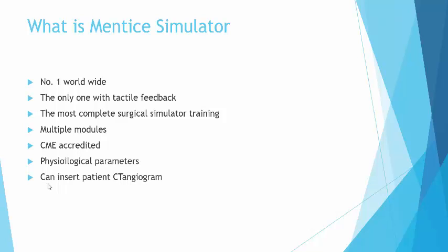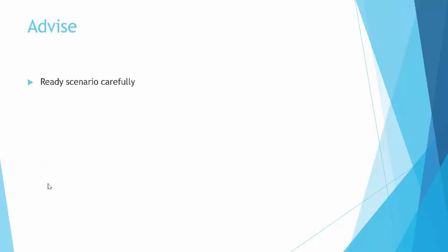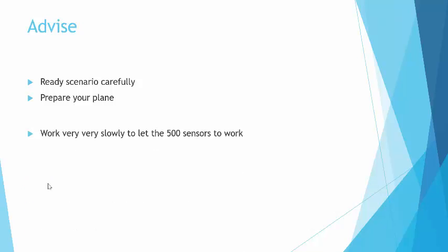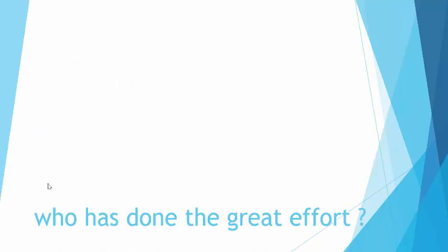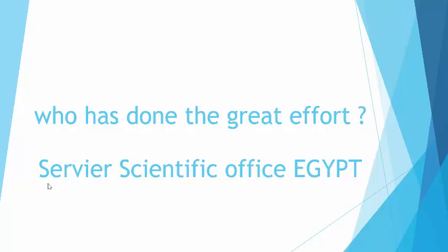My advice is read the scenario carefully, come to the simulator room 15 minutes before your time to prepare your plan, do the sizing and actual measurements, and please have slow movements because there are more than 500 sensors inside the machine. If you have rapid movement it will cause glitching in the machine and you will not get good advancement of your catheter.